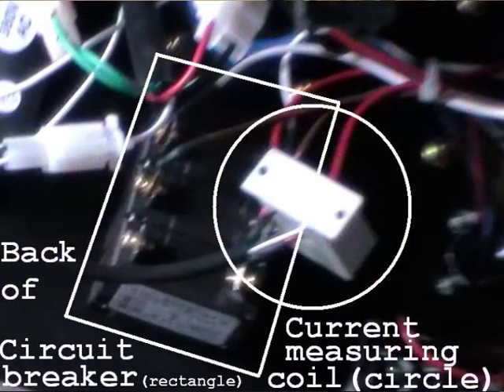So that current clamp failed to detect any current going through that particular wire, and that particular wire is just attached to one phase. I don't think there's any doubt that what I was doing to the milling machine was putting a significant load onto the generator, as the generator was clearly struggling. So we definitely know there was a load on the generator, and yet there was nothing showing on the ammeter. This, I think, has turned out to be fortunate for me, as it has diagnosed the fault.